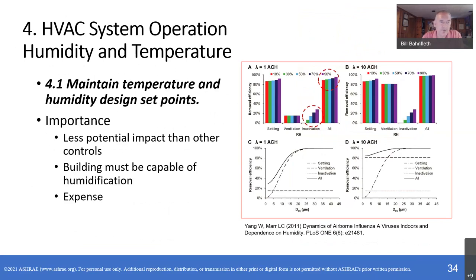With respect to temperature and humidity control, we recommend for the pandemic maintaining temperature and humidity design set points that are existing. So if buildings are humidified, that's great. ASHRAE recommends humidifying between about 30% and 60%. But if a building isn't humidified, that's not the first thing that we would recommend.